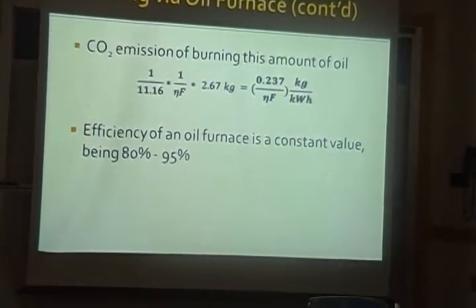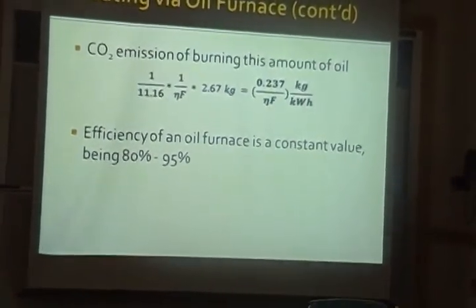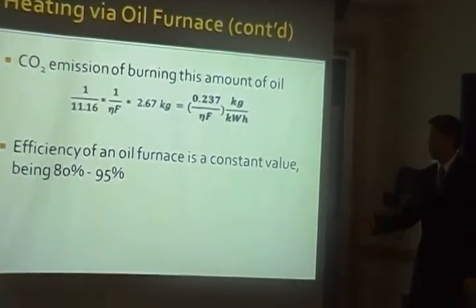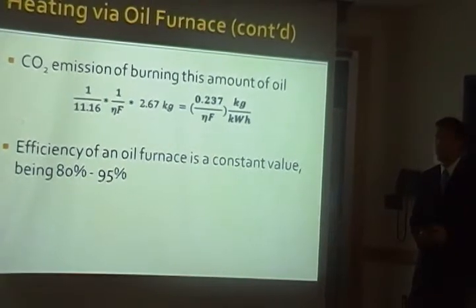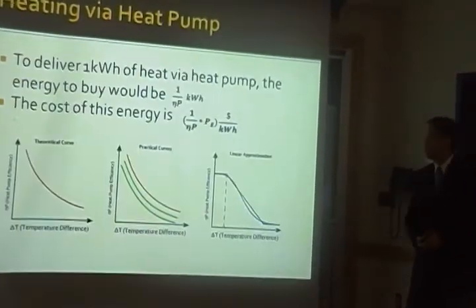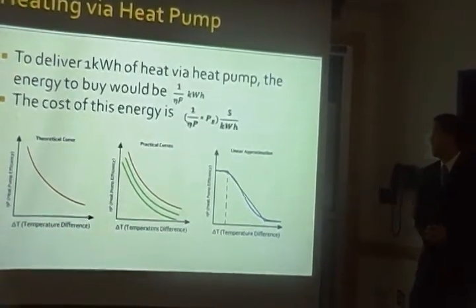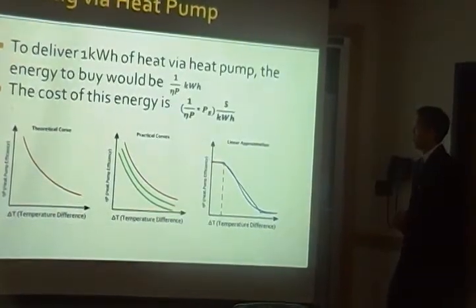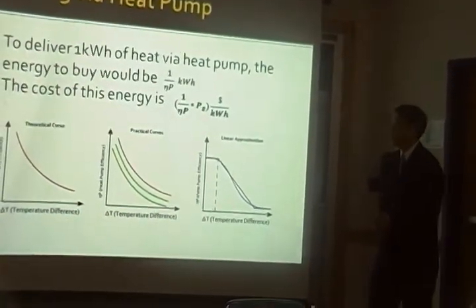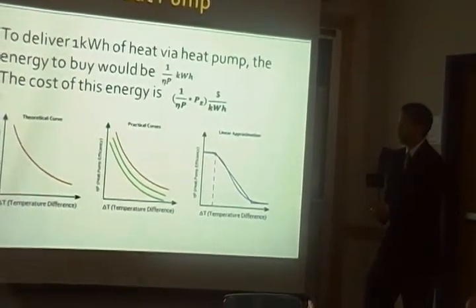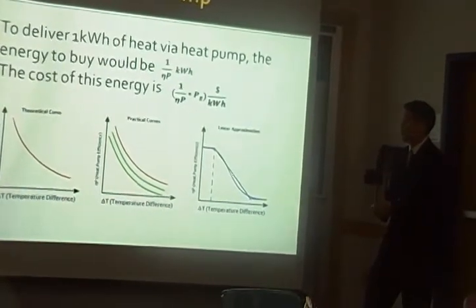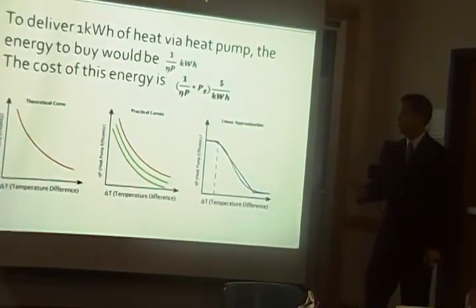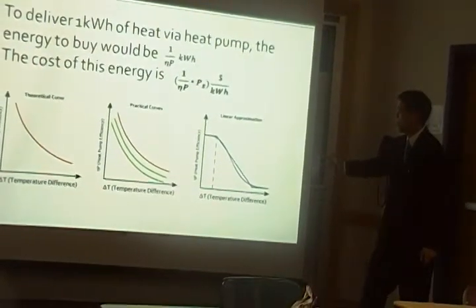We also determined the carbon dioxide produced from burning that amount of oil using a standard equation. The efficiency of an oil furnace is a constant that varies from furnace to furnace, ranging from 80% to 95%; for our system we used 85%. For the heat pump, the energy to buy per kilowatt-hour of heat delivered is also the inverse of the pump efficiency, and the cost is the unit price multiplied by that. The heat pump efficiency follows a theoretical curve showing that as temperature difference increases, efficiency decreases. We took an average of practical curves from real heat pump machinery and applied a linear approximation for our algorithm.